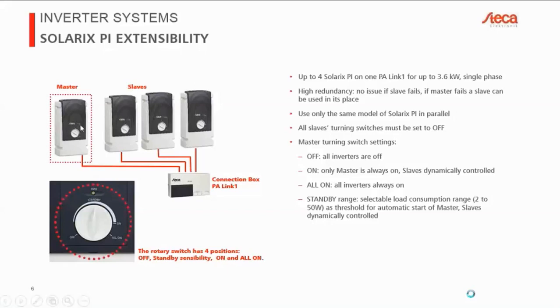And even if the master fails, which is basically controlling all the others, then basically you only need to switch out the communication cable and the AC cable on the PA Link 1, and then you can go ahead and fix the master or whatever, if it's a warranty case, depending. But like this, if you're on a critical site, you can continue to run it by simply taking one of the slaves and replacing the master with it. So the units are always identical. It's just a question of where you connect them on the PA Link 1.